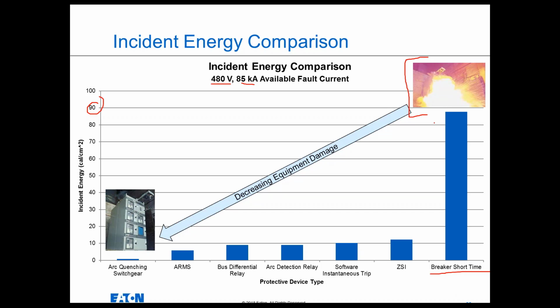That is performing arc-resistant testing on non-arc-resistant gear and holding in that fault for a full 30 cycles. So definitely worst-case scenario, but the equipment's completely destroyed. Then on the other extreme is that same test performed on our quenching switchgear, 480 volts, 85 kA, a 30 cycle arcing fault, worst case. And this is a snapshot of that testing at that same moment in time. Pretty marked difference between traditional NEMA 1 equipment and arc quenching.